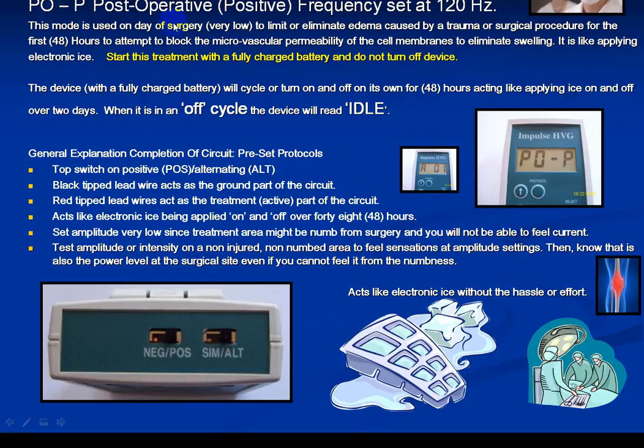If the current is alternating, it can create an alternating squeezing, pumping contraction — like a massage — to stimulate circulation of blood flow and move fluid. Most galvanics are pre-programmed. You can have a pre-programmed edema reduction, chronic pain, or post-op mode, or it can be adjustable depending on what a knowledgeable clinician wants to do for specific purposes. A pre-programmed mode is already set at the required polarities and frequencies.